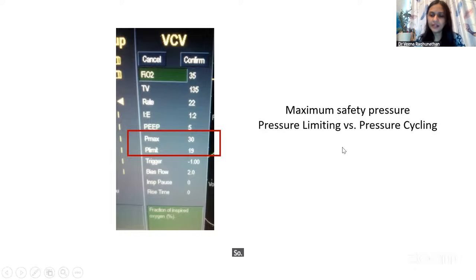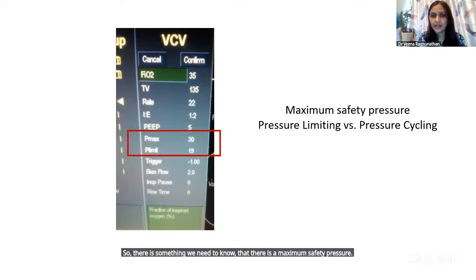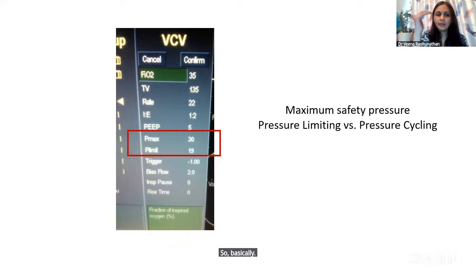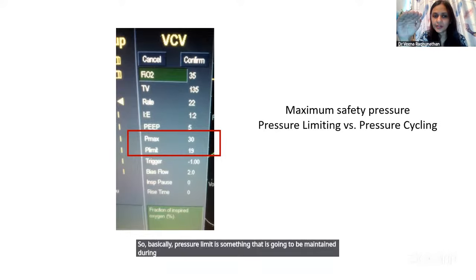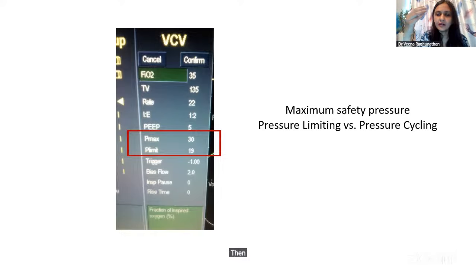There is something we need to know: there is a maximum safety pressure which is available, especially in the volume control modes. Pressure limit is something that is maintained during the inspiration, but we also set a P max, which means that if the pressure exceeds that at any time during the breath cycle, then the ventilator is going to cycle from inspiration to expiration. So that's the difference between pressure limit and pressure cycling.